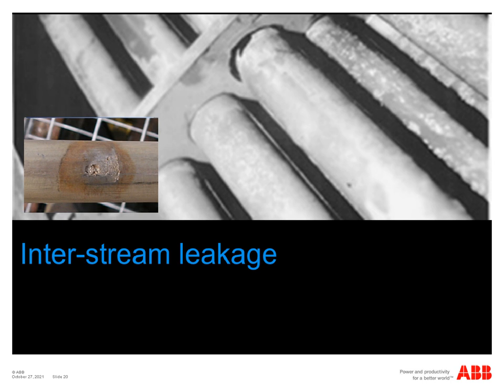So moving on to interstream leakage. For shell and tube heat exchangers, tube rupture is a relatively rare event, but incidents have occurred, so it is a credible event that could happen. So some possible outcomes of this are as follows. You could have release of material from the shell side gaskets. That's assuming the shell side is the lower pressure side, which it normally is, but not always.